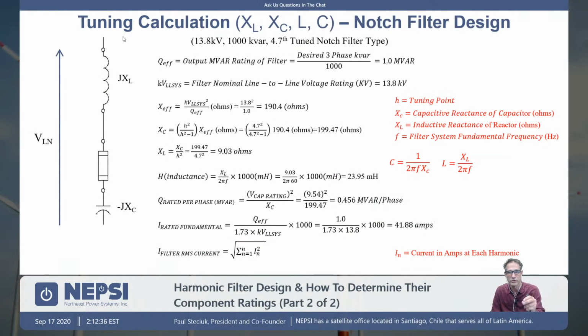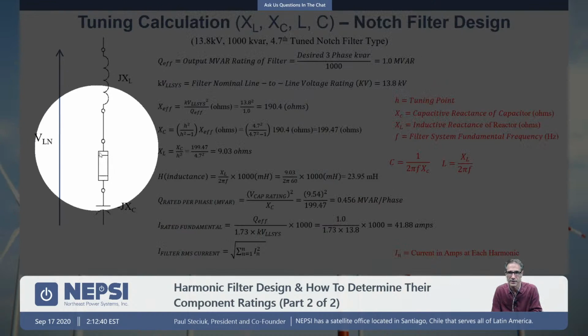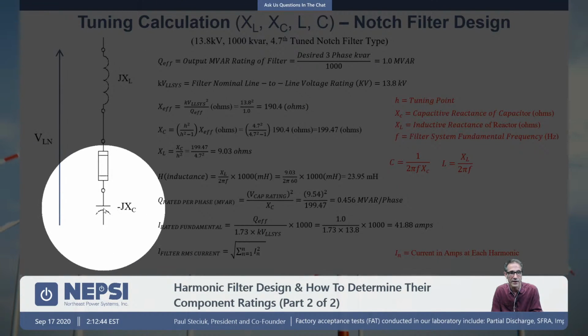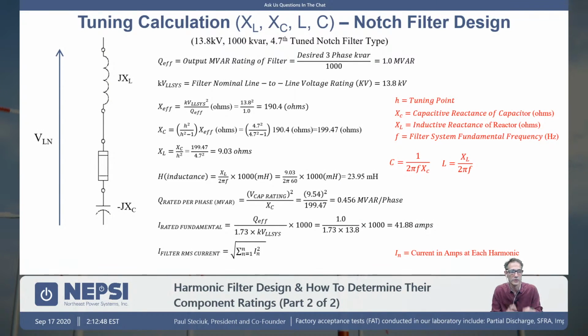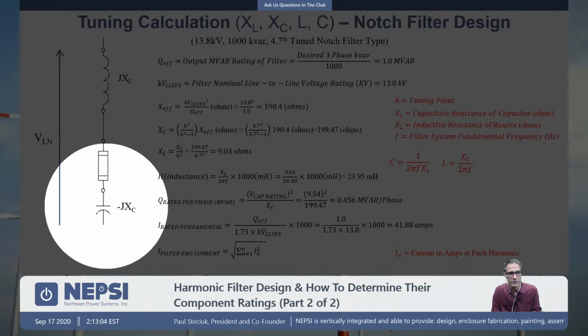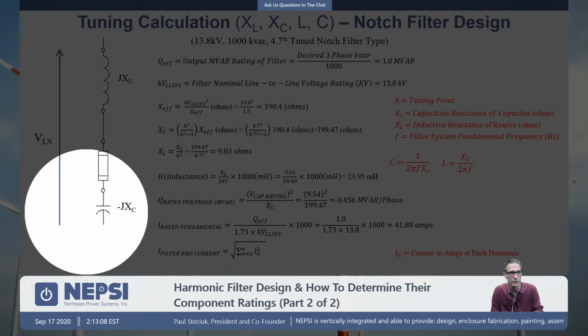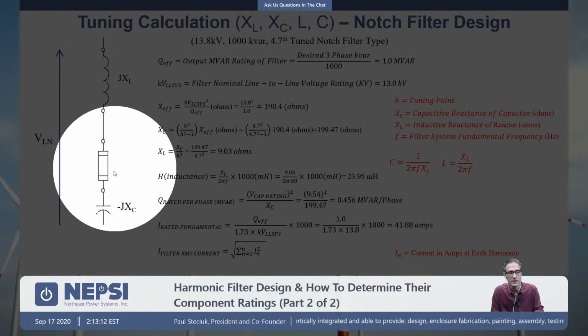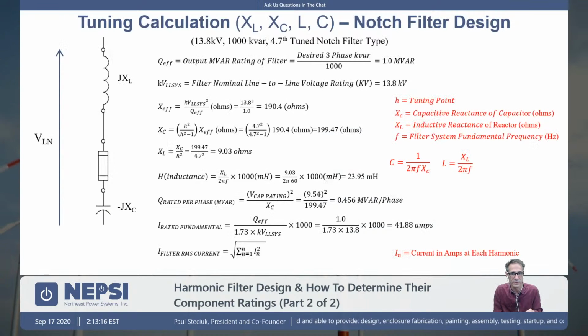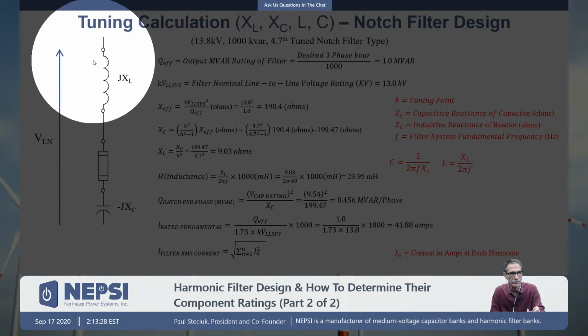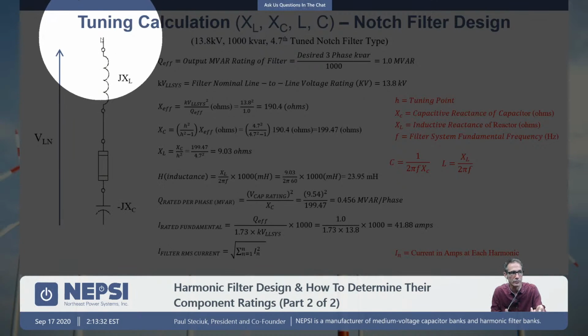When you're specifying harmonic filters, always remember there's an installed kVAR, which is based upon the capacitance here, and capacitors are always rated by voltage rating, terminal to terminal, which is typically like a line to neutral value, but not typically in a filter, slightly off of that. And it's kVAR rating. So you got frequency, you got volts, and you got kVAR rating, bushing to bushing. And so normally when you look at a harmonic filter, the installed kVAR is always greater than the output kVAR here. We're going to have a higher installed kVAR. So when you're specifying harmonic filters, be sure to distinguish between installed kVAR within the capacitor itself and the effective kVAR, the kVAR output of the harmonic filter. If I put terminal voltage here, what is the kVAR output? And really, that's a key filter parameter.